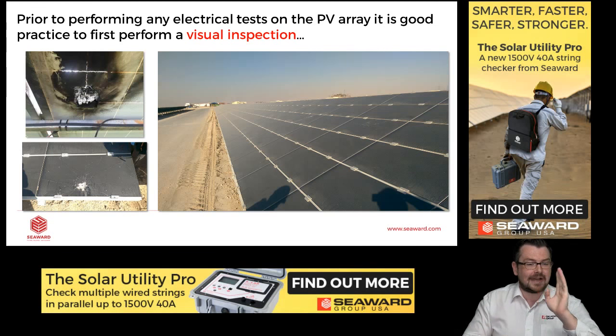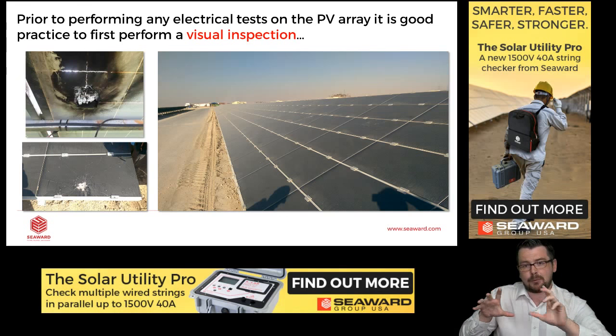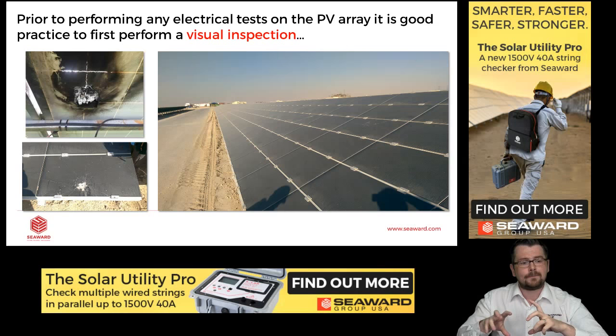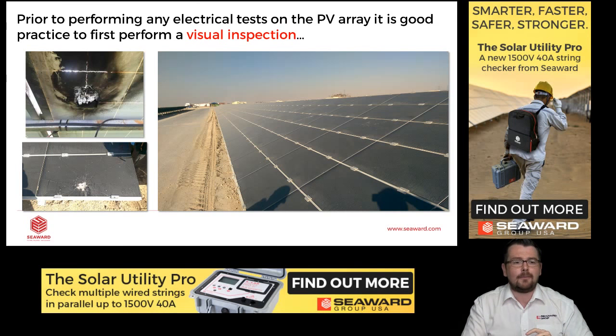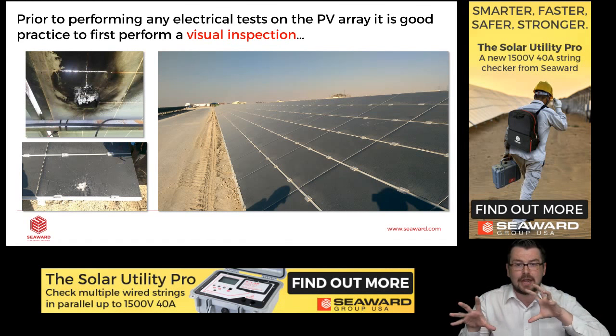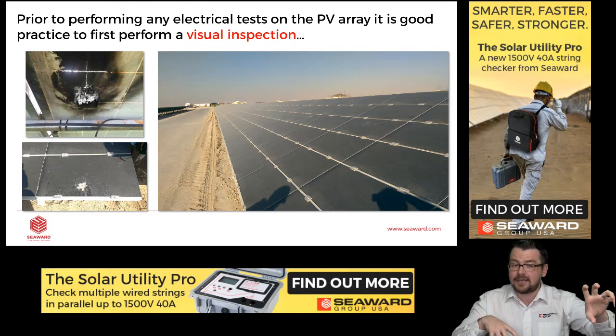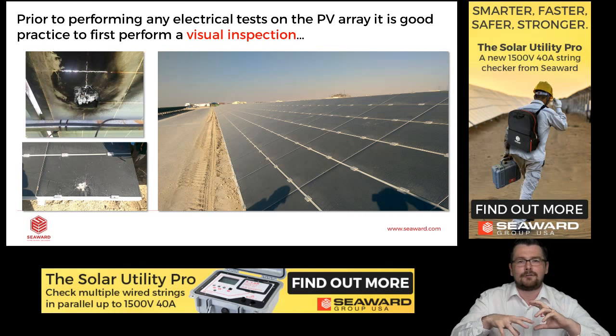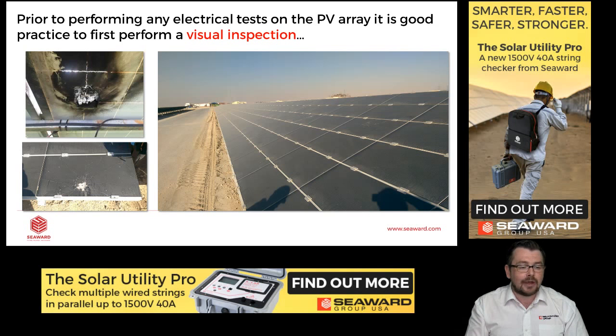So it's always good just to have a walk up and down the table to see if you can see any problems with the front of the modules first of all. So we're looking for cracks, we're looking for spotted shading, which could be bird droppings or leaves, and we just want to maybe clean that off and just make sure that we're going to be testing a nice clean array, which I will also cover shortly.